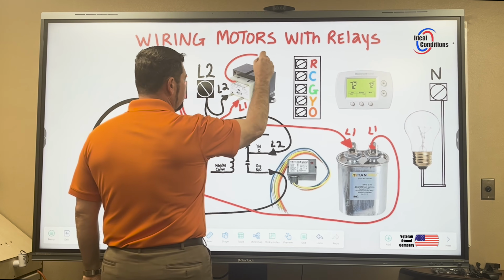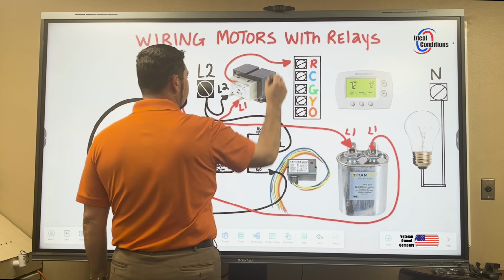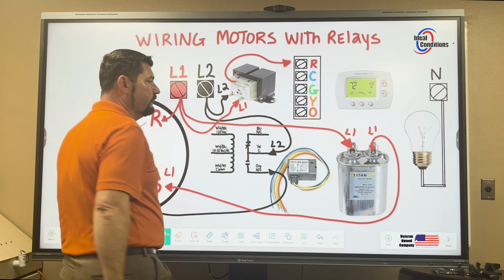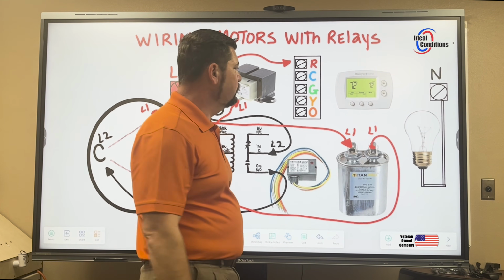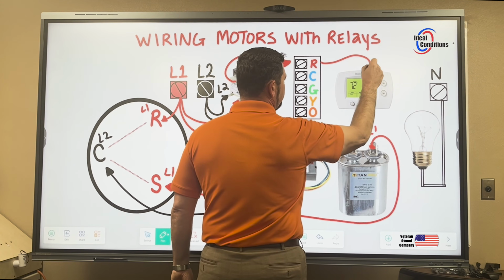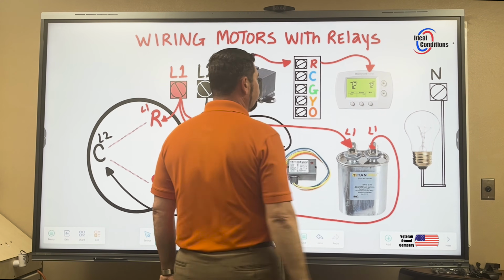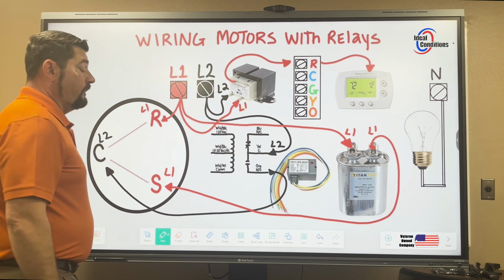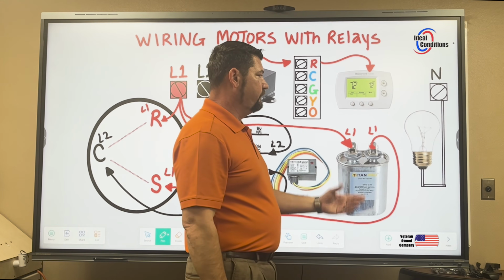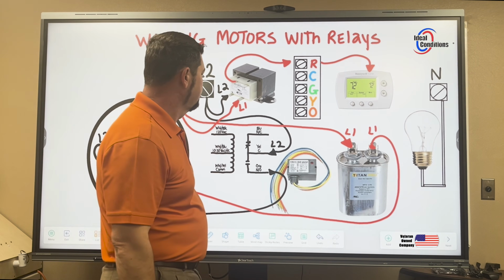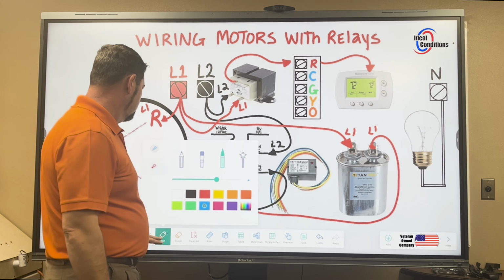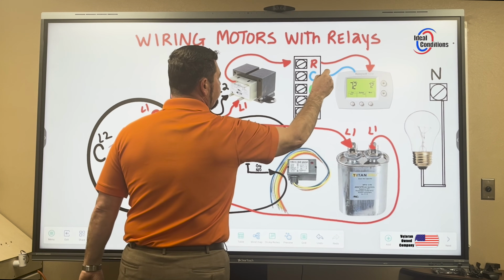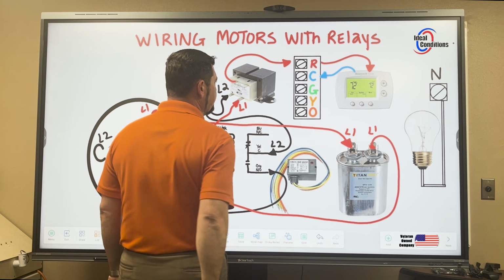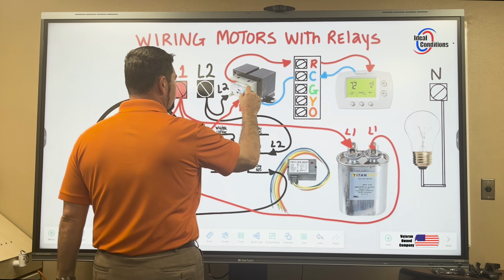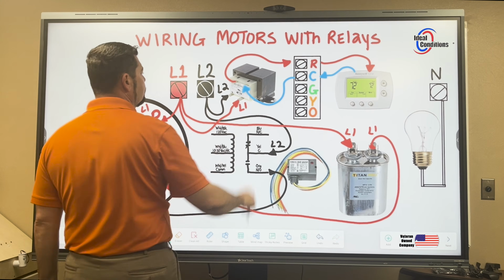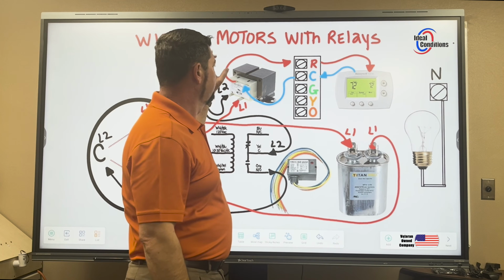We're going to come out and put 24 volts on our terminal block. There's no inline fuse here. Again, it's not a 90,000 hour video. We're going to come out of this terminal block and we're going to energize the float switch. I'm sorry, not the float switch. You should go through your float switch, then go to your thermostat. But we're going to go to our thermostat, and then out of our thermostat, we're going to come back with common if there's no DC voltage for a display like batteries provide. And we're going to create a path back to the transformer. There we go. And now we have 24 volts. There's our loop. We have a display.